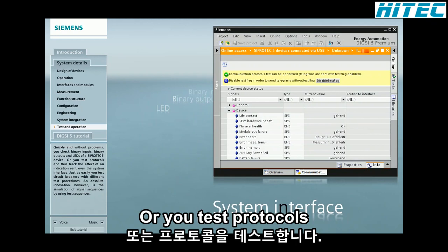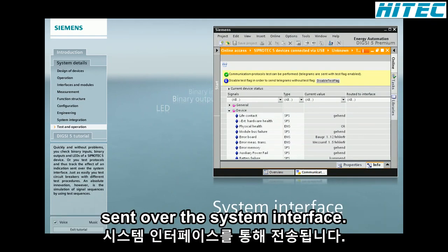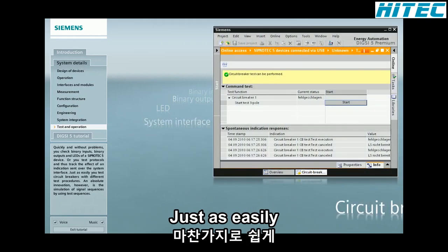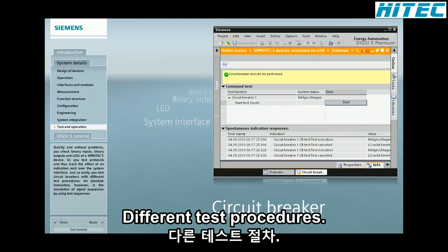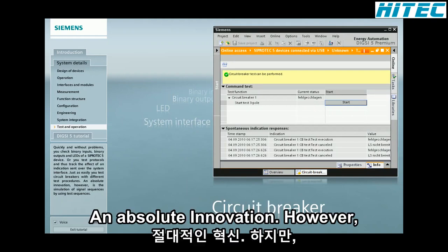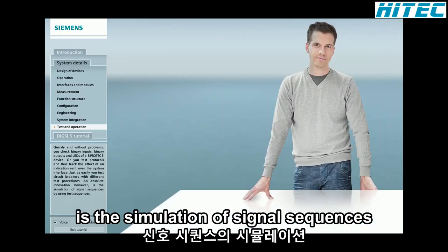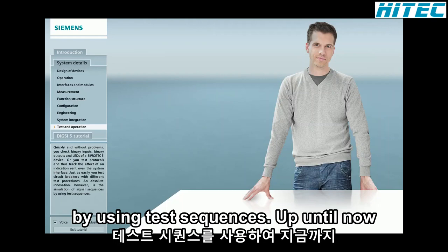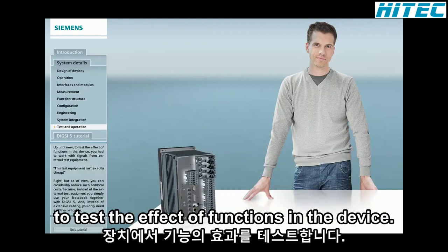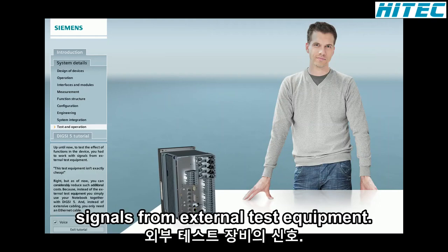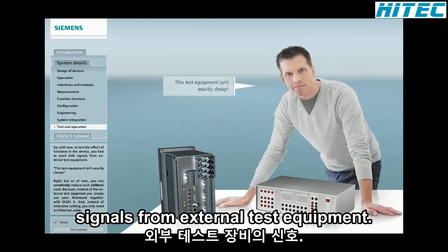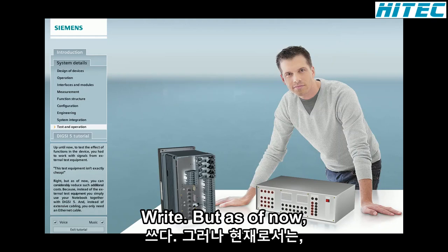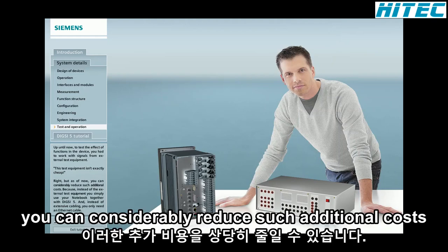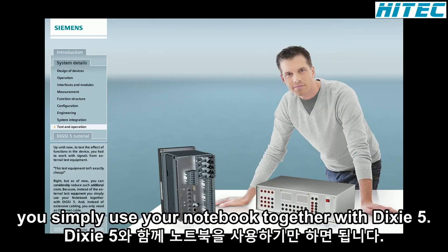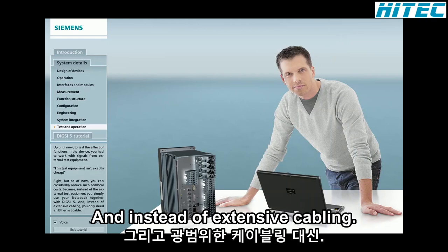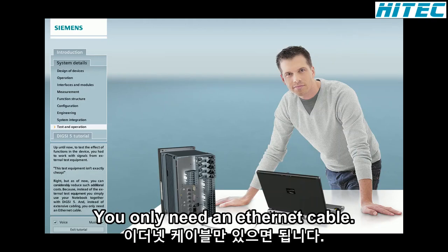Or you test protocols and thus track the effect of an indication sent over the system interface. Just as easily, you test circuit breakers with different test procedures. An absolute innovation, however, is the simulation of signal sequences by using test sequences. Up until now, to test the effect of functions in the device, you had to work with signals from external test equipment. This test equipment isn't exactly cheap. Right, but as of now, you can considerably reduce such additional costs because instead of the external test equipment, you simply use your notebook together with DIGSI 5. And instead of extensive cabling, you only need an Ethernet cable.